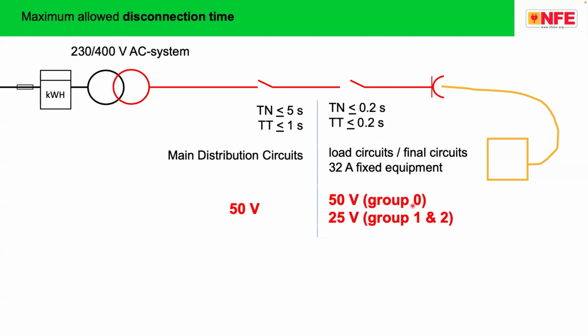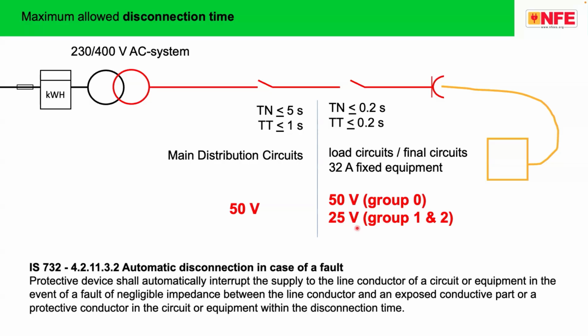50 volt is the allowed shock voltage during fault in group 0 location, and 25 volt is the allowed shock voltage in the group 2 location. Please note that the working voltage of an electrical equipment is 230 volt, but we must make equipotential bonding in such a way that the maximum allowed voltage is 25 volt in group 1 and group 2 locations.